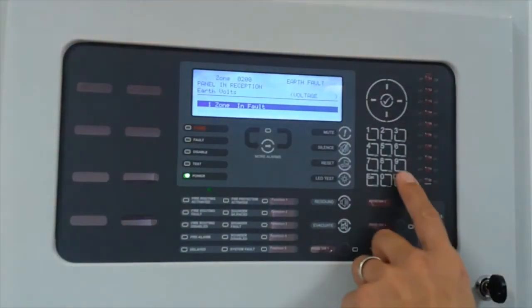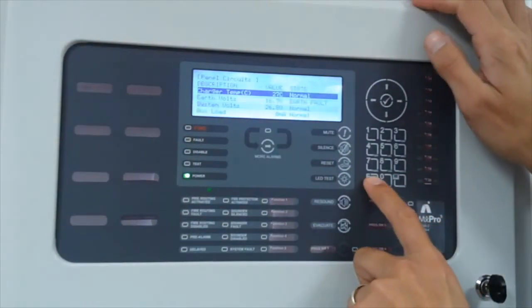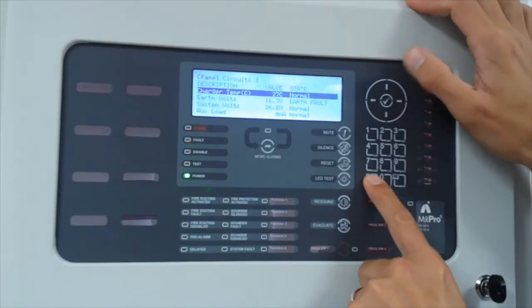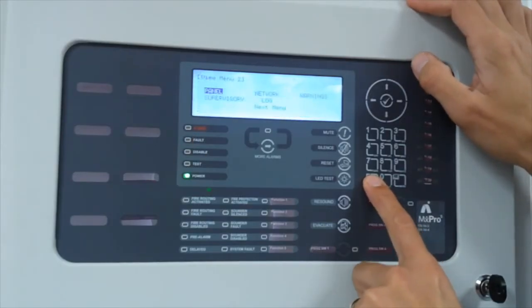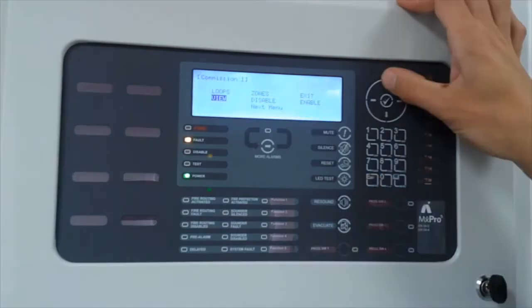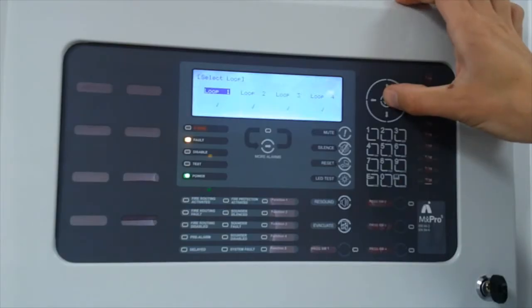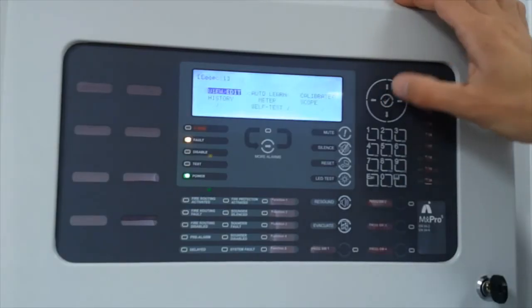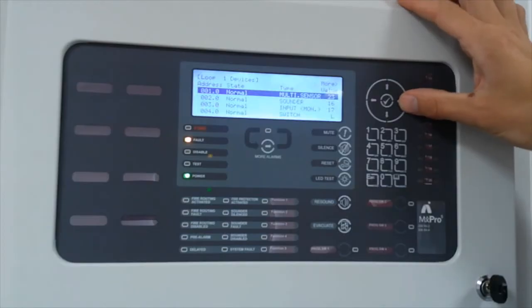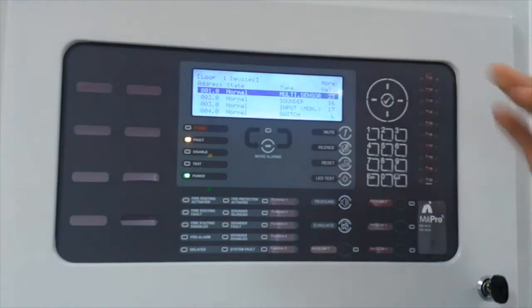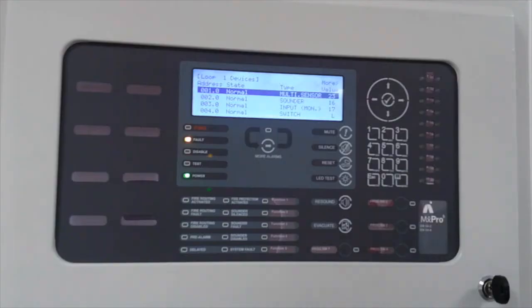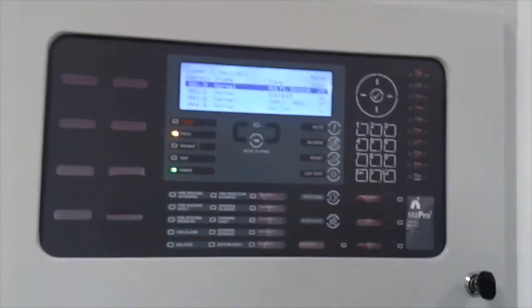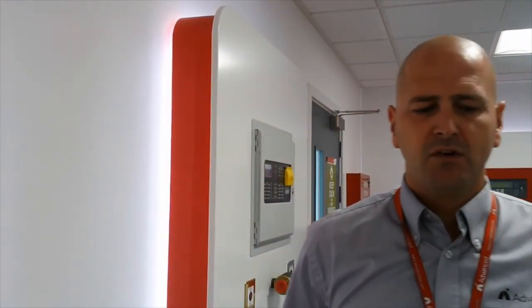The next option is then put the panel into commissioning menu. We know it's on loop 1. We go to the loops, loop 1, identify your devices, making sure you've got the relevant information. One of the key points now is basic fault finding techniques. So one of the important rules to remember, put the panel into commissioning. Okay, so we put the panel into commissioning.